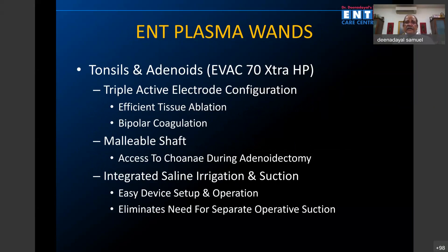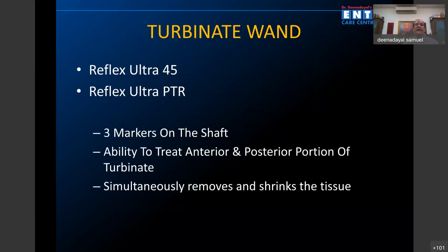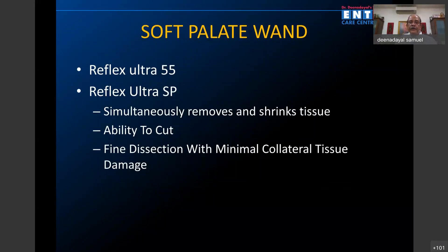There are different wands available. The commonest one is called the EVAC 70 Xtra HP — considered the workhorse. It has a triple active electrode, a shaft that you can bend, can be used in adenoidectomy, and has complete integrated saline and irrigation. There are also turbinate wands: Reflex Ultra 45 and Reflex Ultra PTR, which I will show in videos demonstrating how they are used.